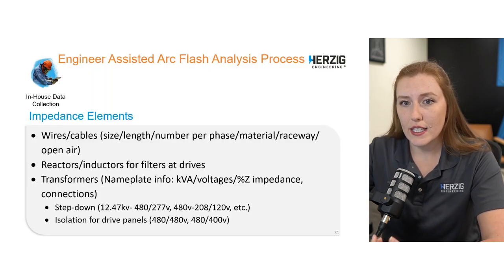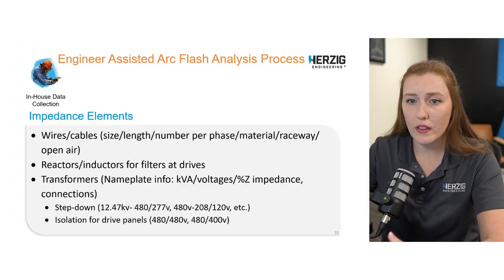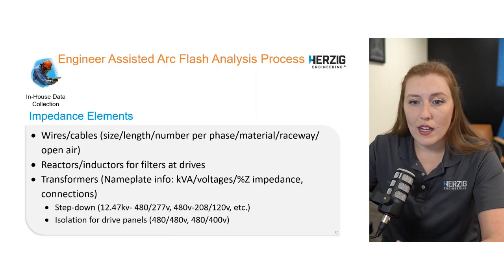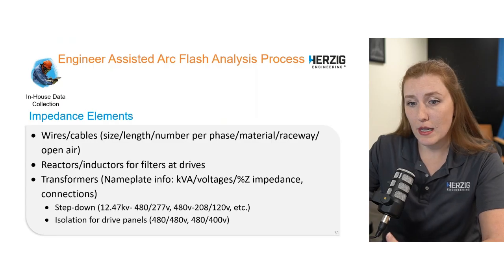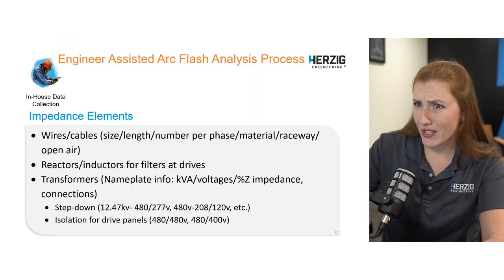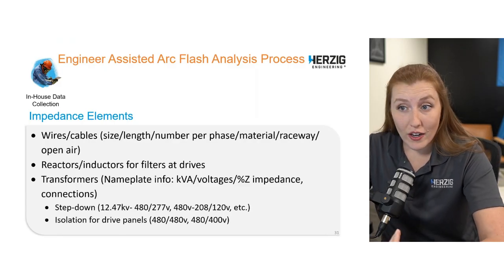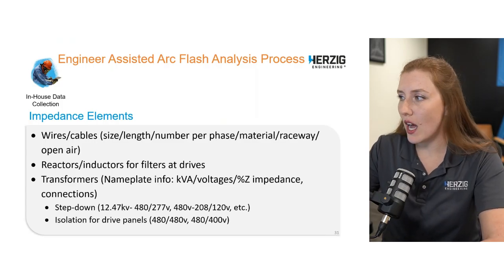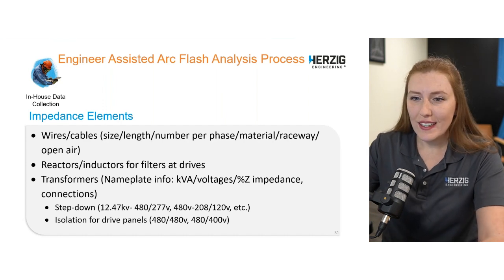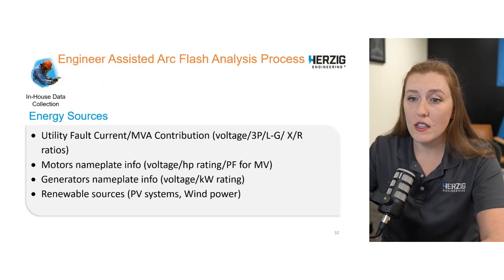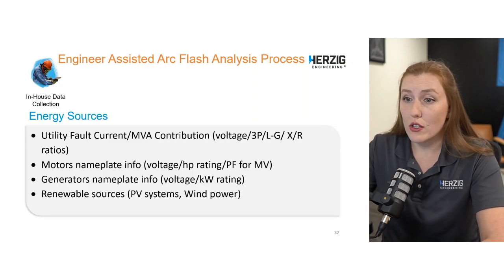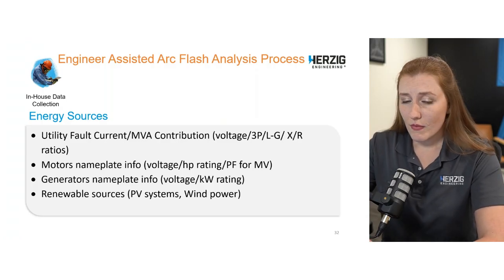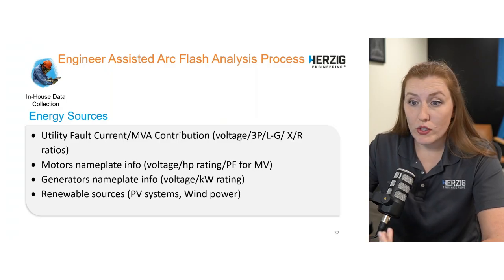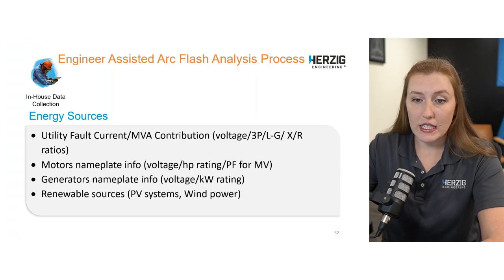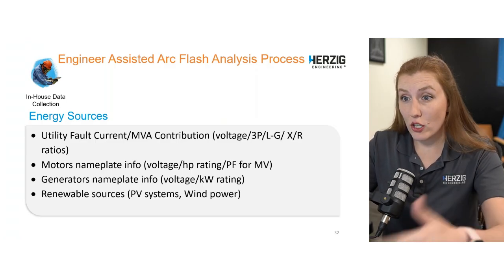Okay, so the kinds of things that they're going to be collecting. Like I said, the impedance elements, the energy sources, such and so forth. So wires and cables, reactors and inductors for filters and drives, transformers, we need the nameplate info, so the kVA, the voltages, is it stepped up, stepped down, is it an isolation or buck boost transformer, what's the percent impedance for that, the percent Z. For the wires, how long are they, how many per phase, what type of wire is it, aluminum, is it copper, is it 500 kcmil, is it 4-aught, what is it? All of that needs to be included in the data, as well as those energy sources. So utility fault currents, whether it be the MVA or kVA, the voltage, is it 3-phase, line to ground, what are the X/R ratios? If you have that information, motor nameplate info, voltage, horsepower, power factors, generator nameplate, kind of same ideas here with renewable sources, all that energy that could get inputted into the system.